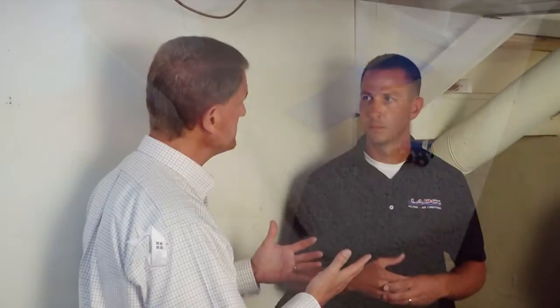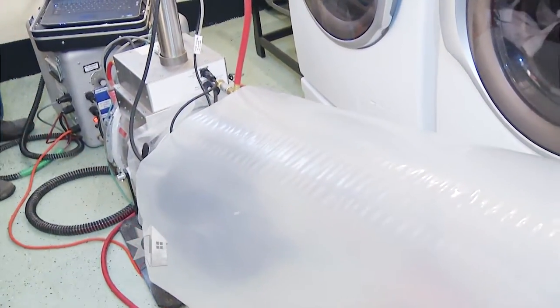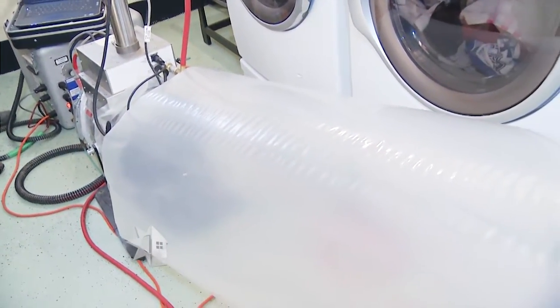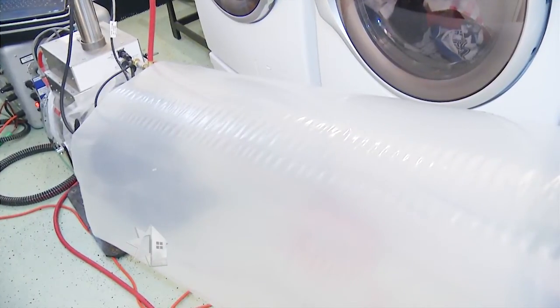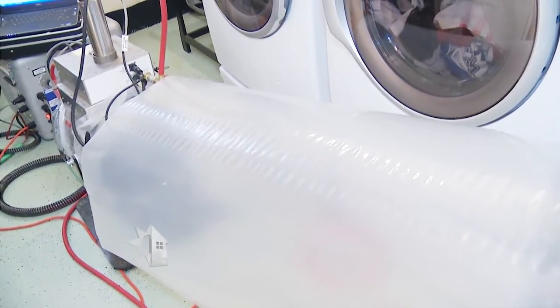It's called AeroSeal - that's the sealant being injected into the system. Once the foam pads are in place, we start up the remainder of the equipment, including the heater assembly and the injection wand, which forces the sealant, along with the fan box, into the ductwork.